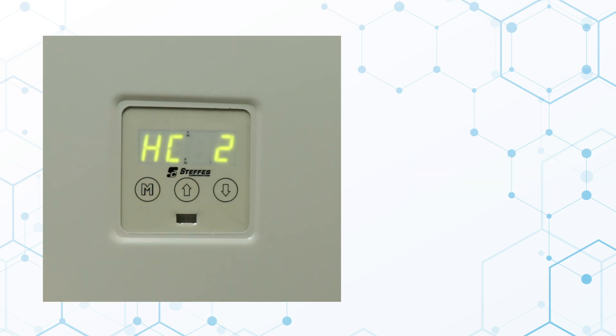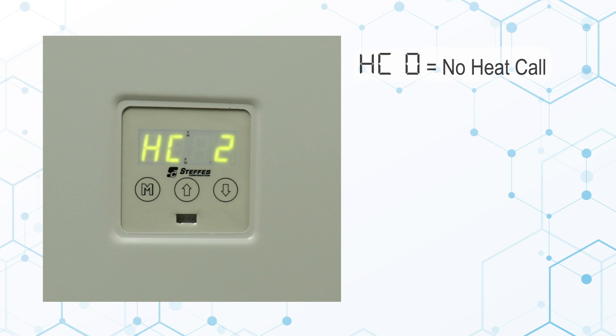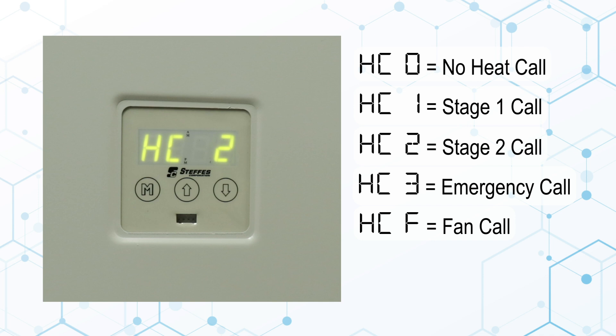Press the up arrow again. The display will show HC and a number. This indicates what stage of heat call the furnace is currently receiving from the thermostat. The display can show a 0, 1, 2, 3, or an F for a fan call.